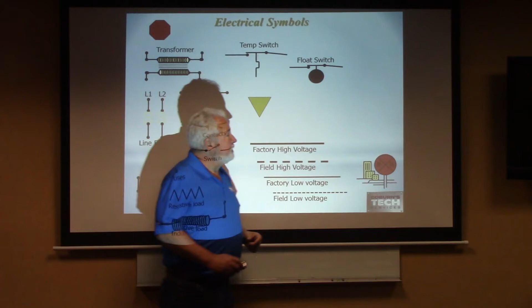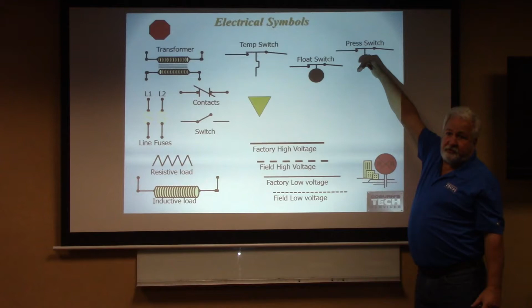So this would be a high pressure switch. If the pressure got too high, it would open up. If it was a low pressure switch, it would be drawn down here at the bottom, and when the pressure started dropping off, it would fall open. Does that make sense, the difference between a high pressure and a low pressure switch?